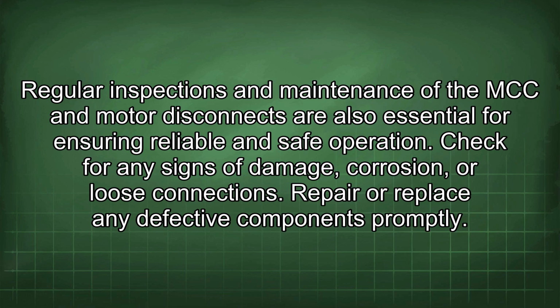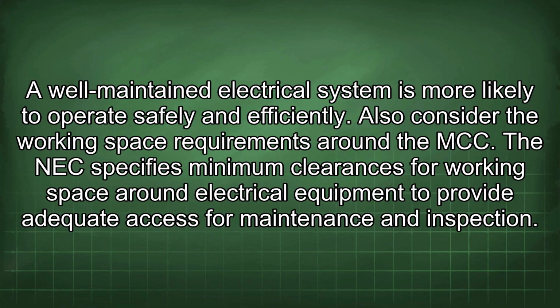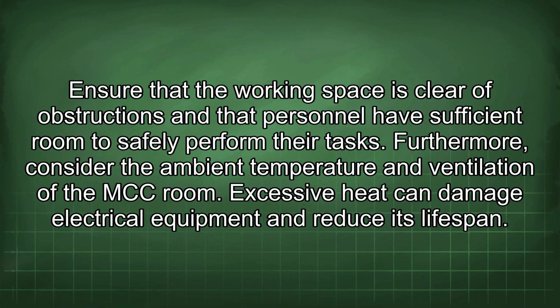and safe operation. Check for any signs of damage, corrosion, or loose connections. Repair or replace any defective components promptly. A well-maintained electrical system is more likely to operate safely and efficiently. Also consider the working space requirements around the MCC. The NEC specifies minimum clearances for working space around electrical equipment to provide adequate access for maintenance and inspection. Ensure that the working space is clear of obstructions and that personnel have sufficient room to safely perform their tasks.